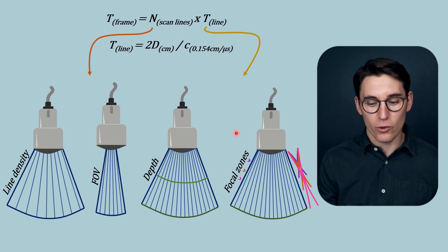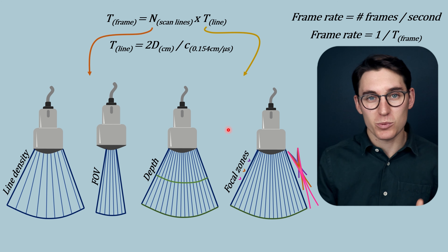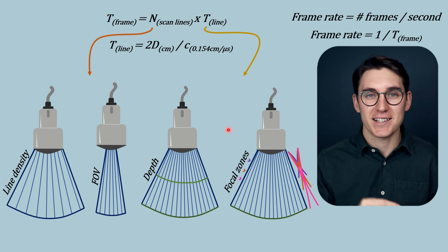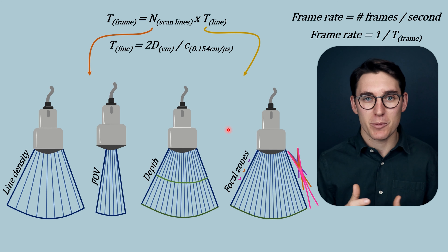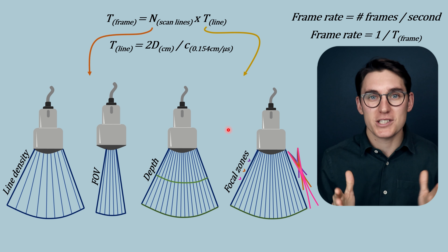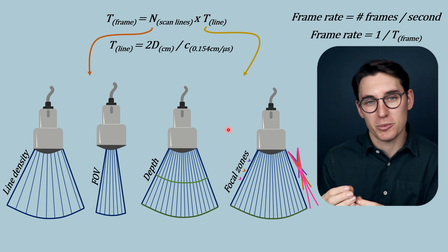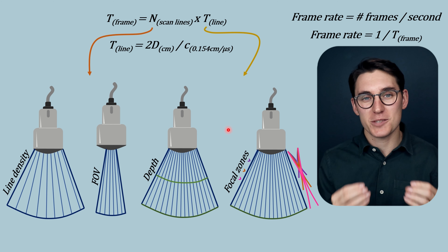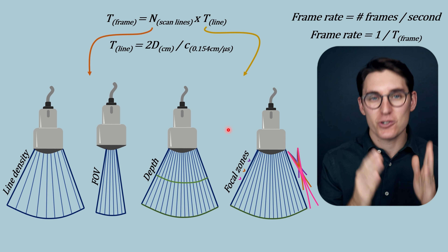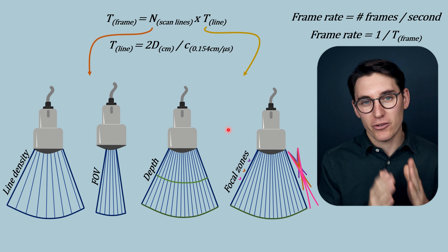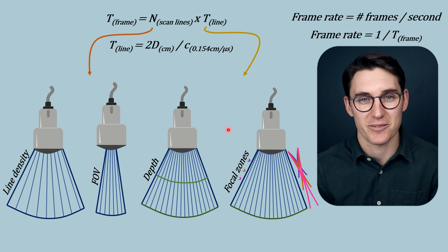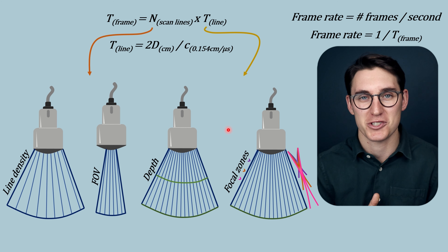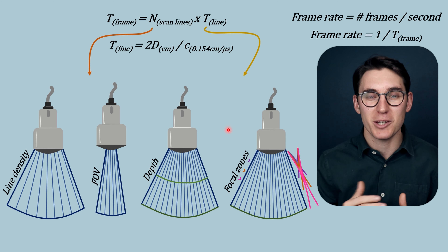Knowing these parameters and how they affect frame rate is all you need to understand temporal resolution. To get the best temporal resolution, image at the shallowest depth possible, with the smallest field of view, fewest focal points, and the least number of scan lines. Changing these parameters comes at a cost, and we need to trade off what is more important — is lateral resolution more important, or are we trying to track fast movements? Hopefully by now you have a good conceptual understanding of axial, lateral, elevational, and temporal resolution, and which factors to change to manipulate resolution.